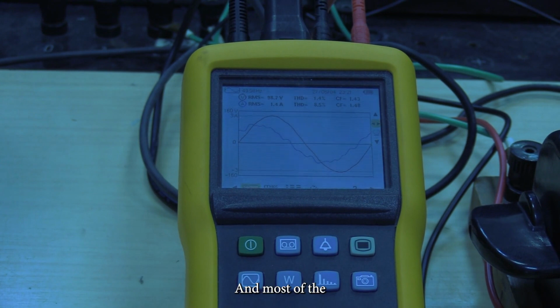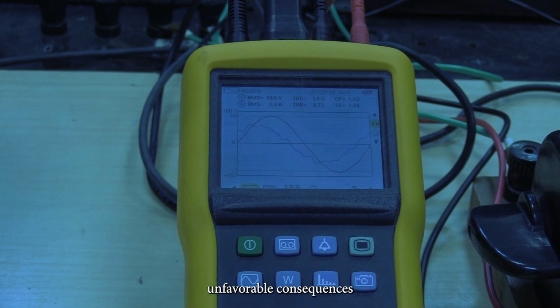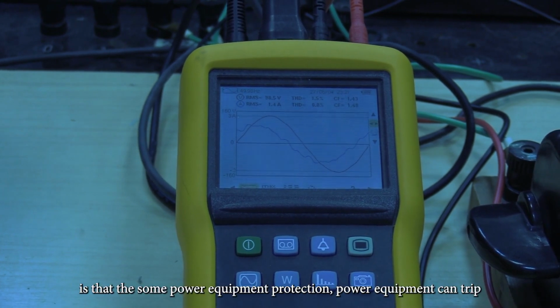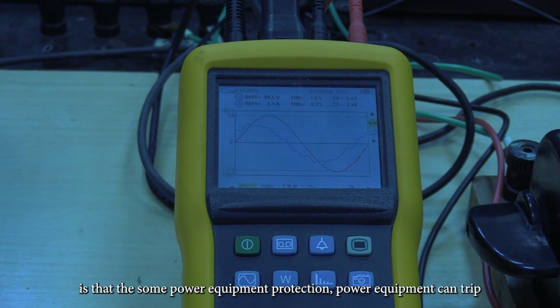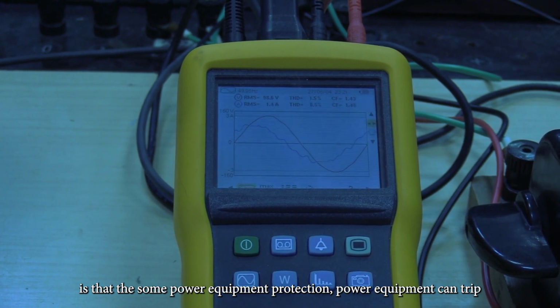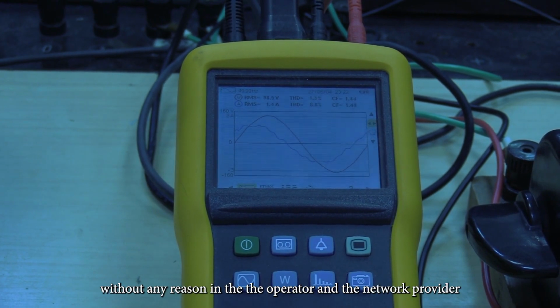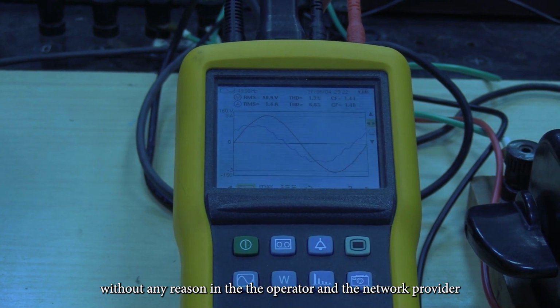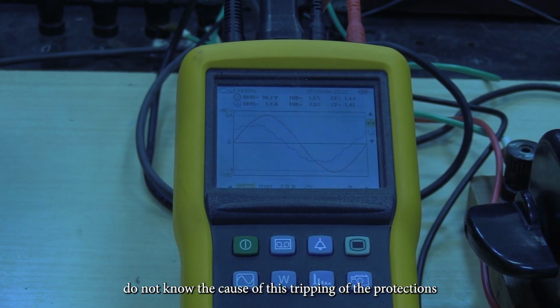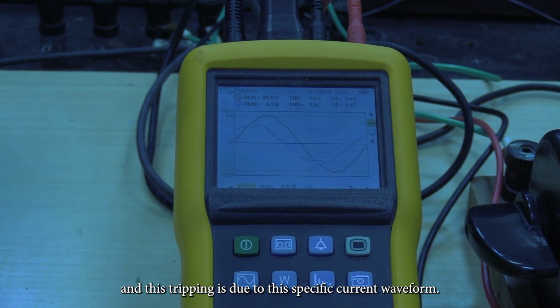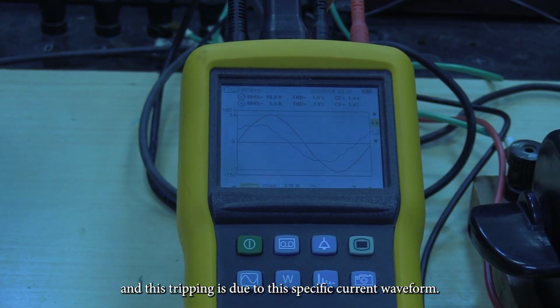And the most unfavorable consequence is that some power equipment, protection power equipment, can trip without any reason. And the operator and the network provider do not know the cause of this tripping of the protections, and this tripping is due to this specific current waveform.